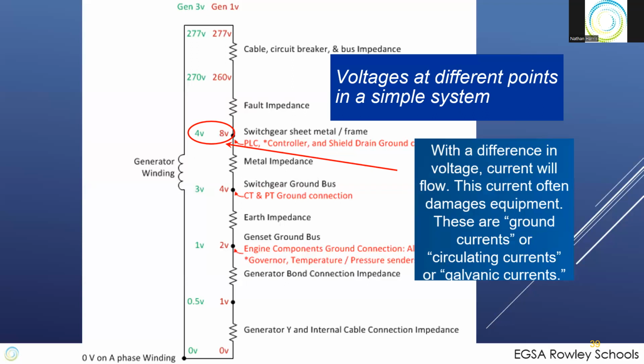And so the 3 volts in generator 1 is 3 volts in generator 3 all the time. And that's not really typical if you're in the real world environment. If it's in a powerhouse where they're next to each other, you can run a big ground bus across the ground, that's probably okay. But if you're a temporary installation with trailers and cables on the ground, that's going to be really hard to get a good solid ground connection. And so you want to be careful of that when you're doing that.